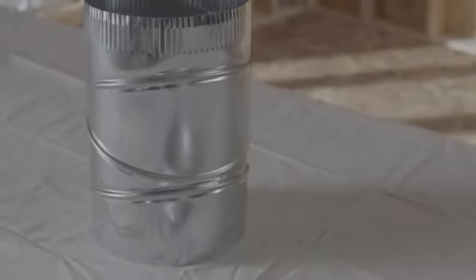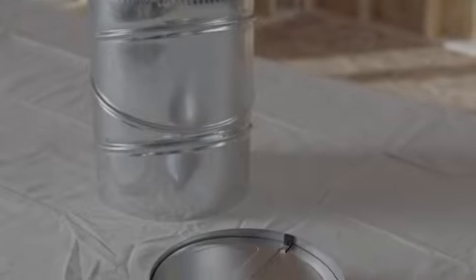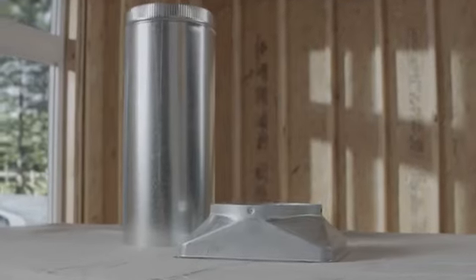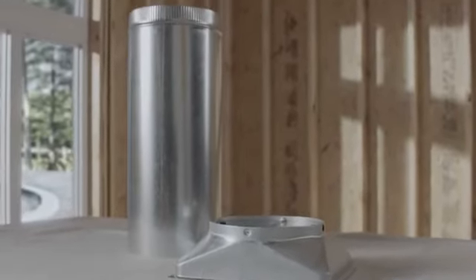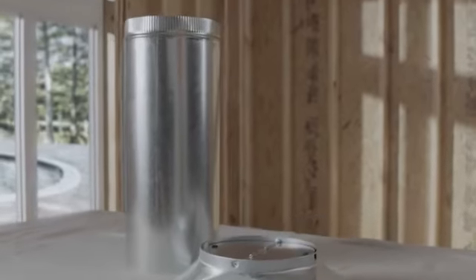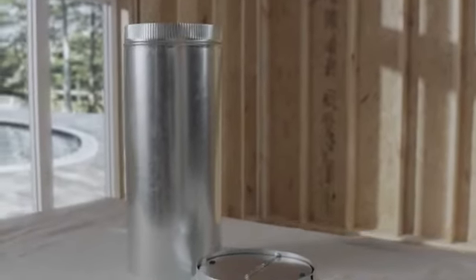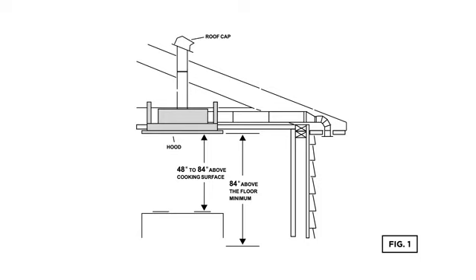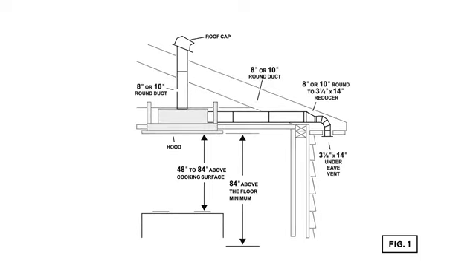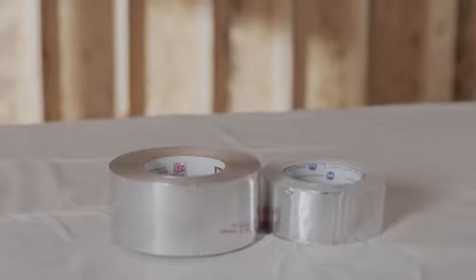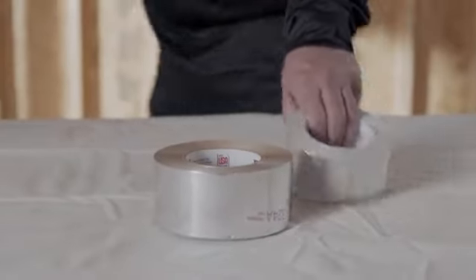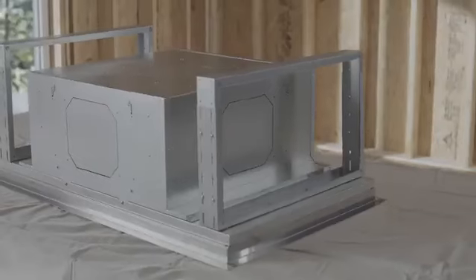Note that a straight, short duct run using 8-inch round duct for a single internal blower or a 10-inch round duct for all other blower types will allow the hood to perform most efficiently. Install a wall cap or roof cap. Then, connect metal ductwork to the cap. Work back toward the hood location. Make sure to use 2-inch foil duct tape to seal the joints between ductwork sections.